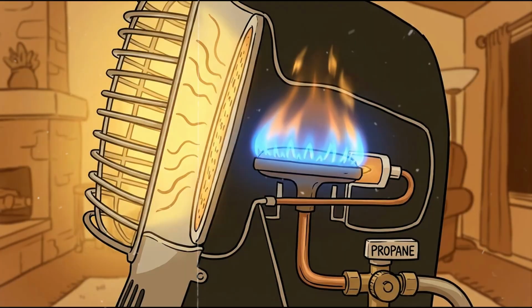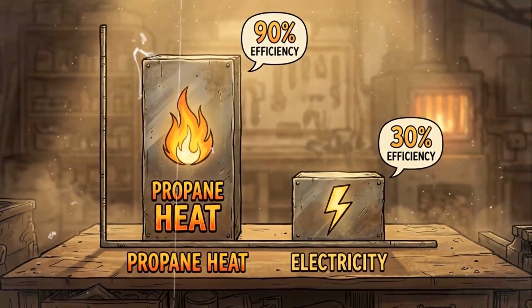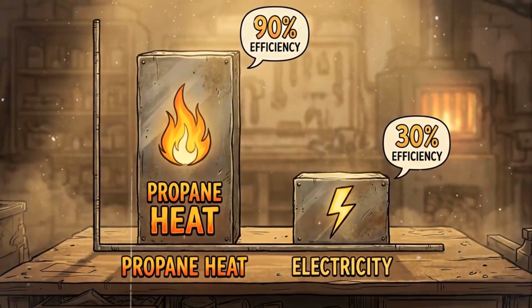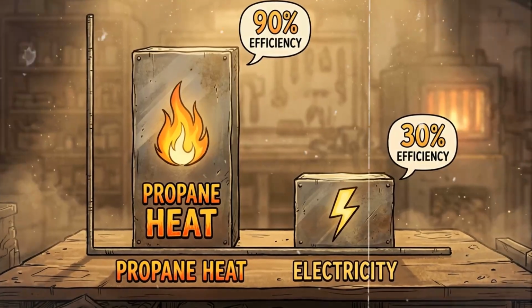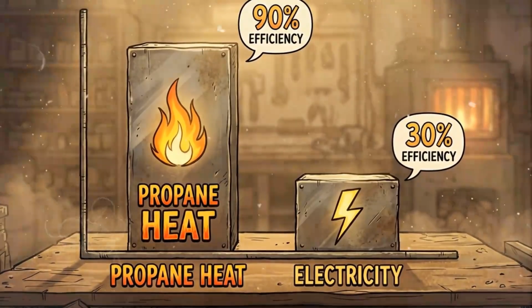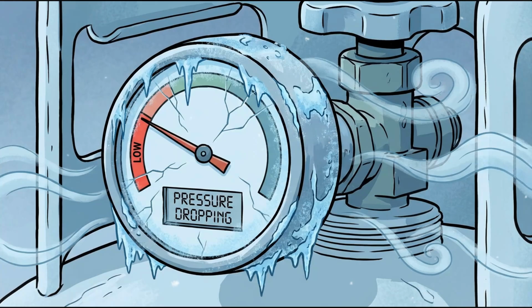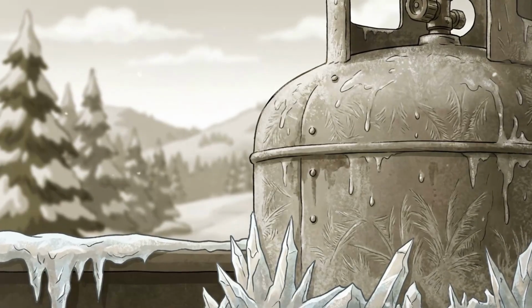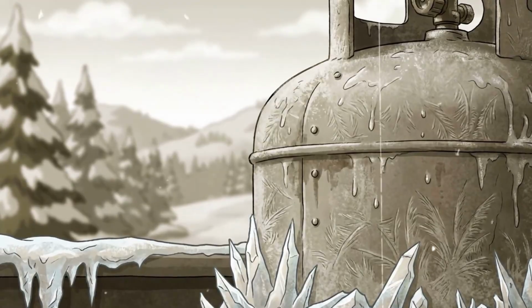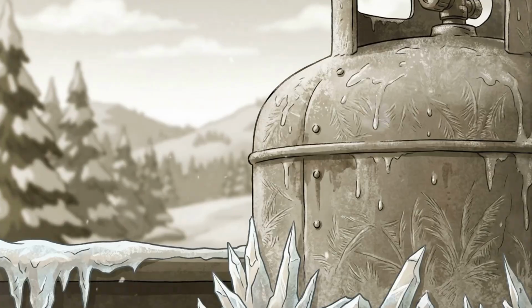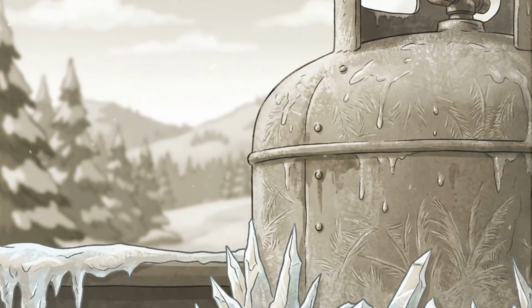For heating applications, which is where propane genuinely excels, the economics shift dramatically. We will cover thermal layer in the next episode in detail, but the summary is this: propane used directly for heat is roughly 3 times more efficient than propane converted to electricity to run an electric heater. If heat is your primary need, do not convert propane to electricity and then back to heat. Burn it directly. There is one propane constraint that matters enormously in cold weather: pressure drop. Propane vaporizes inside the tank to create the gas pressure that feeds your appliance. At very cold temperatures, below -44 degrees Fahrenheit, which is propane's boiling point, the liquid inside the tank cannot vaporize and the pressure drops to 0.